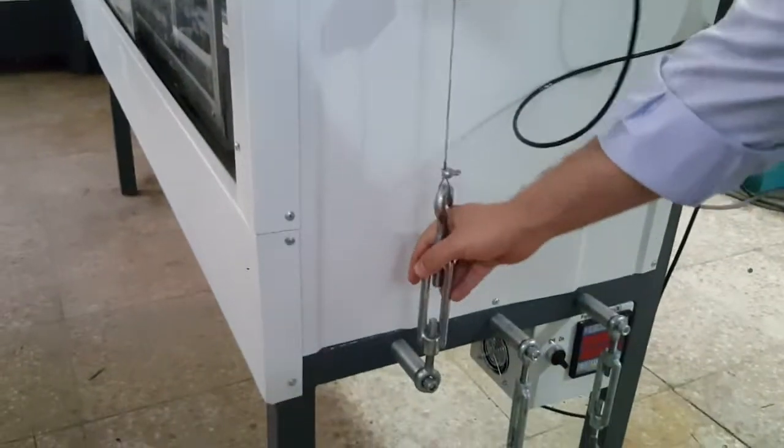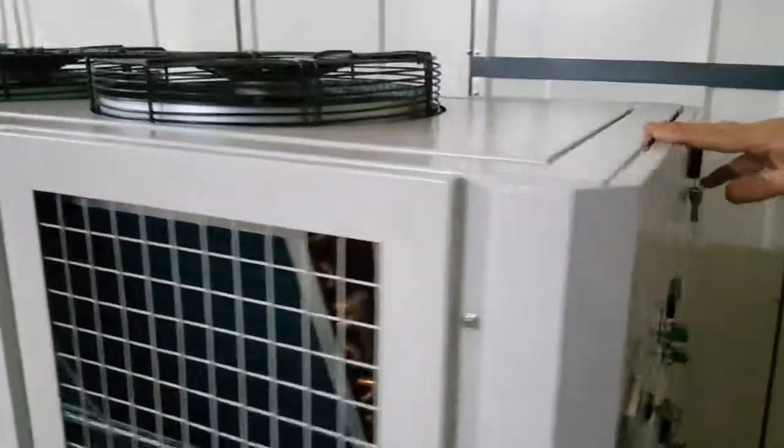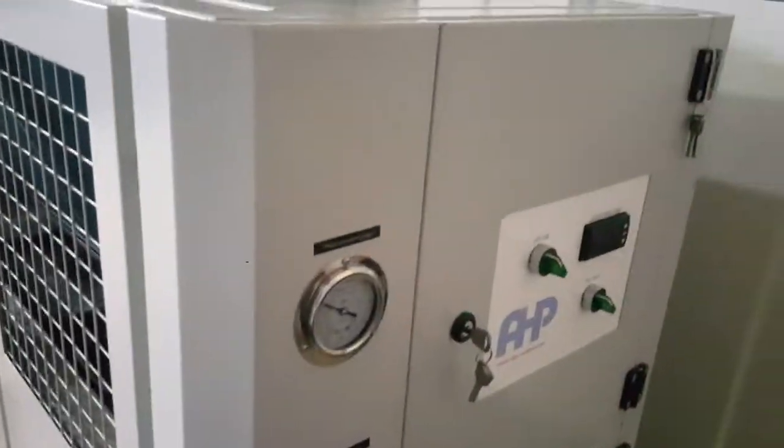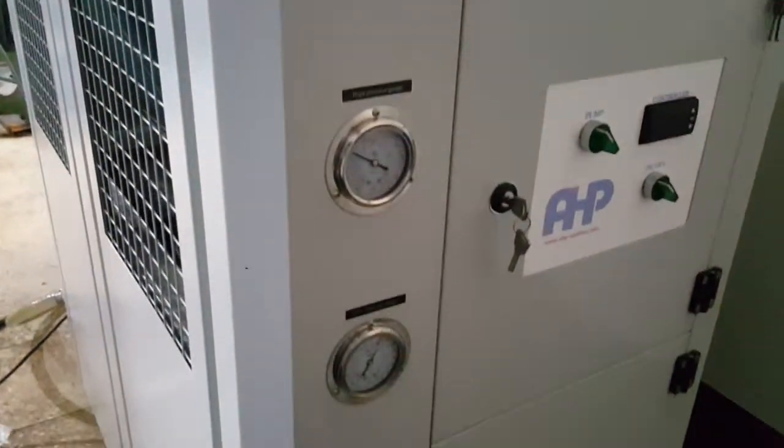We adjust these screws manually. Here, in the back side of the machine, for controlling the temperature of the cold chamber cold tank at 20 degrees, we have a chiller that automatically controls the temperature of the cold tank to 20 degrees centigrade.